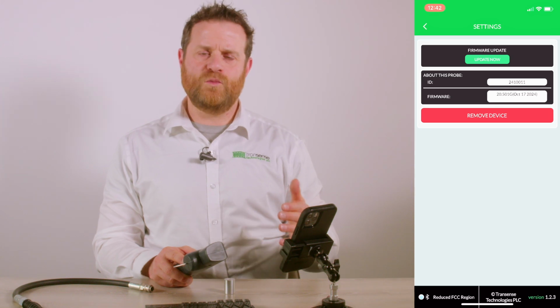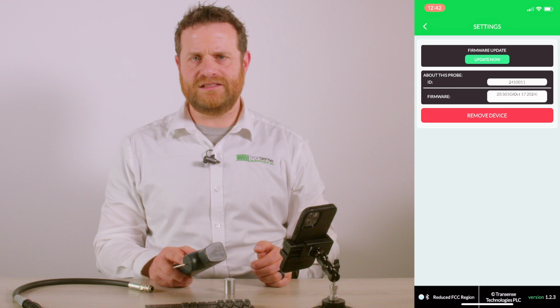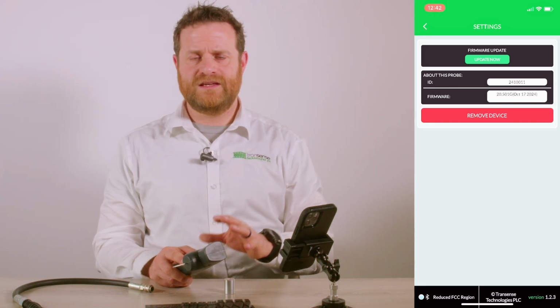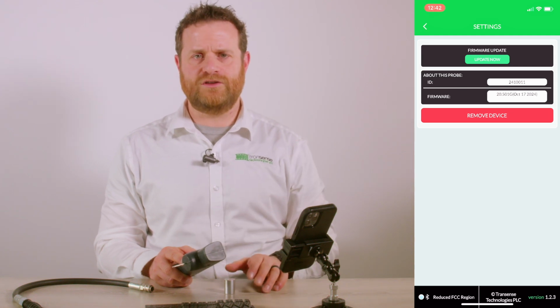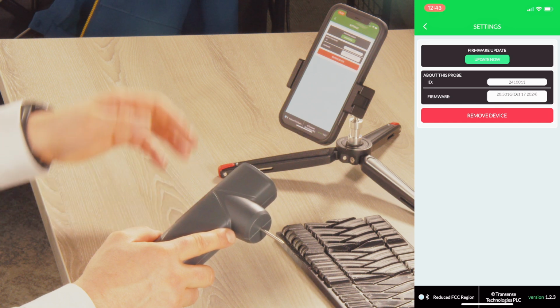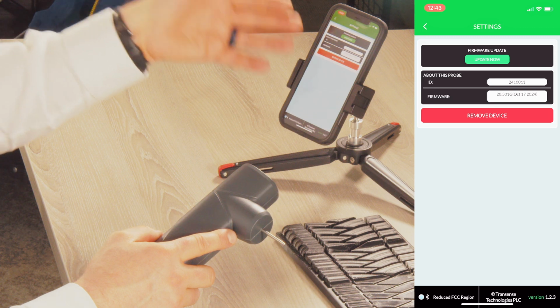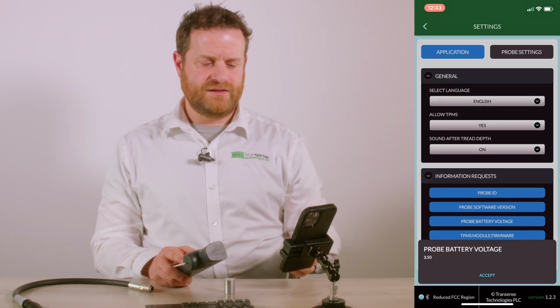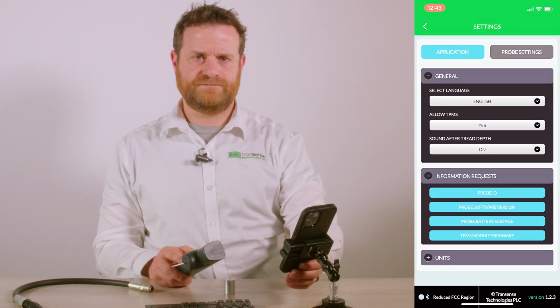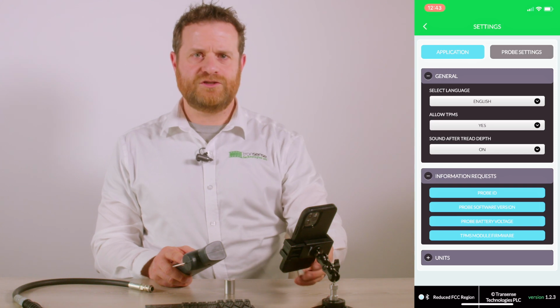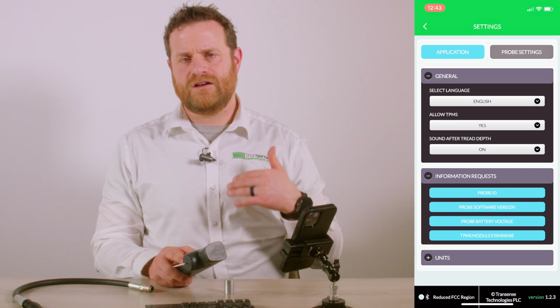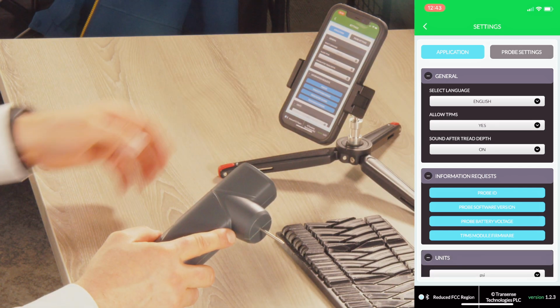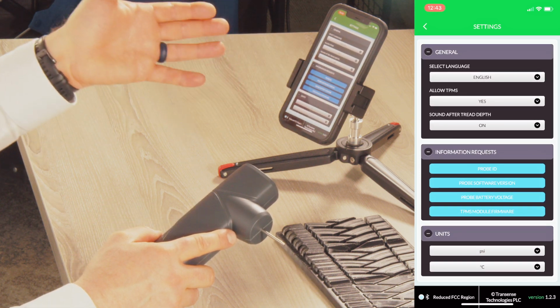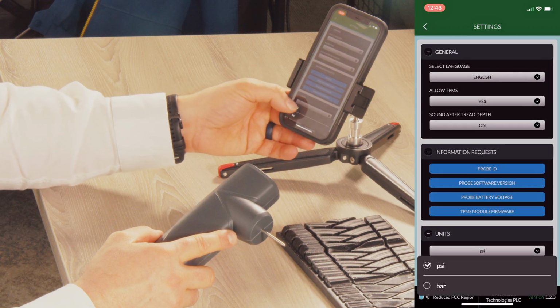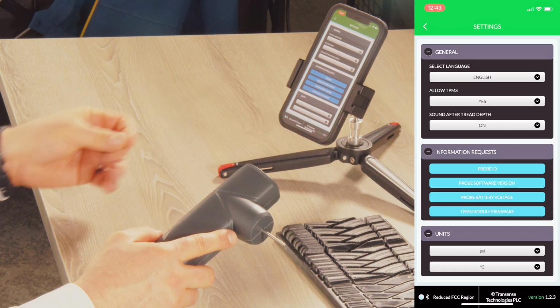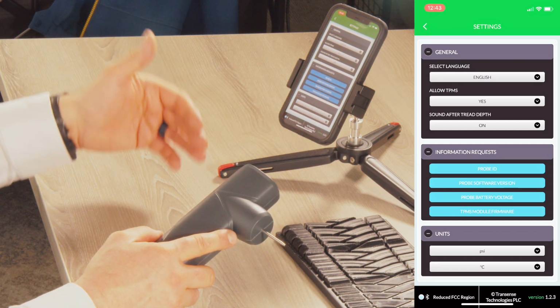Do not attempt to use the firmware update with any file or firmware supplied by a non-trusted source. In some rare cases, the firmware update will get stuck at a 99.9% complete status, but the TLGX tool will disconnect. This is okay, and the disconnection is confirmation of a successful update. In this window, we can also see the serial number of the probe and the current firmware version installed on the device. Probe battery voltage shows the current battery voltage of the device. TPMS module firmware returns the module firmware version installed on the device, on the TLGX4 only. Units can be used to change the units on the QuickCal app from PSI to bar and degrees centigrade to degrees Fahrenheit. Note, this only changes the units on the QuickCal app and not on the TLGX tool itself.